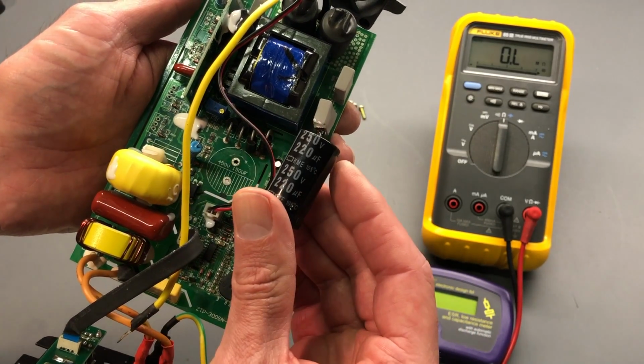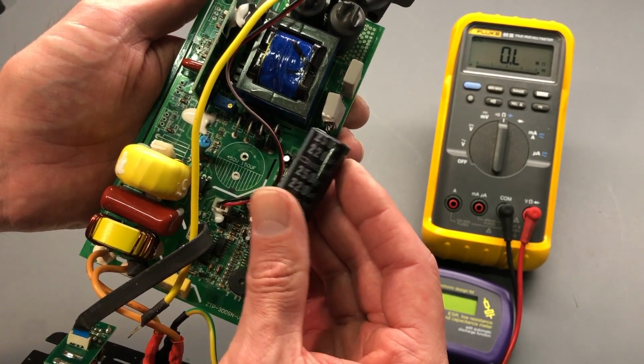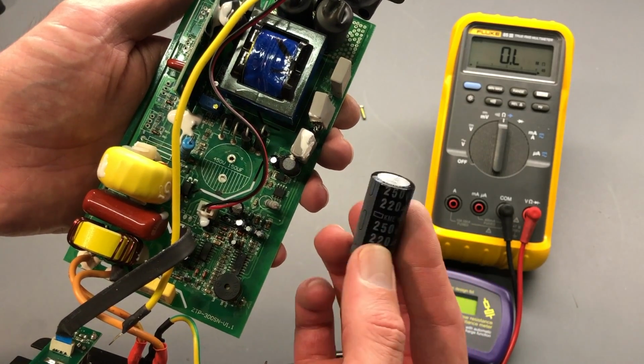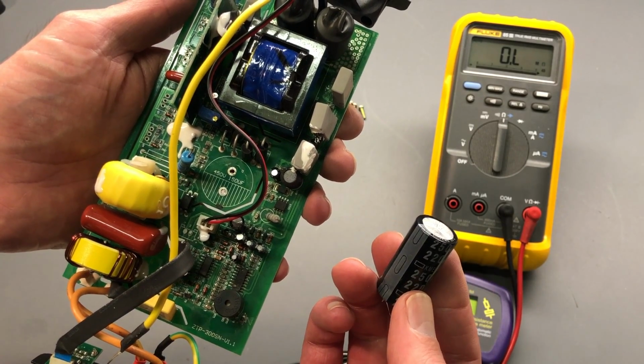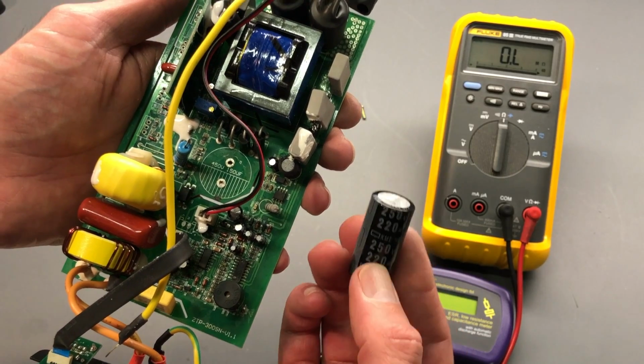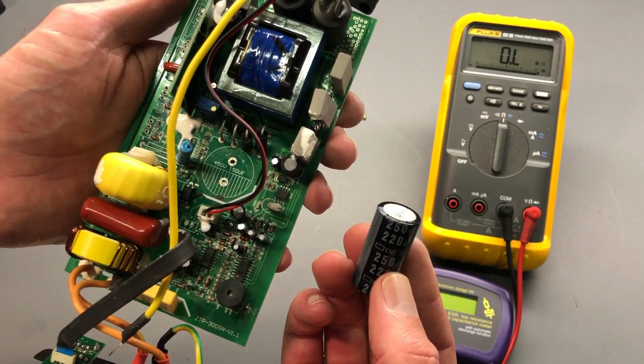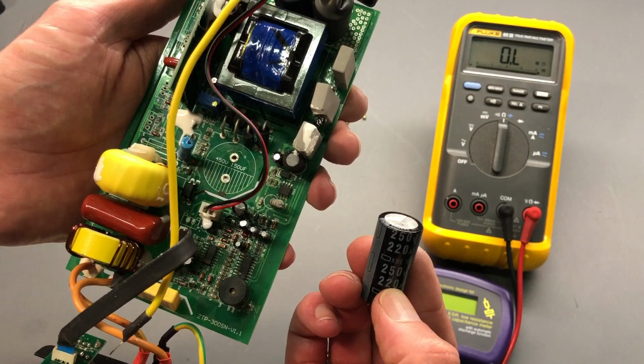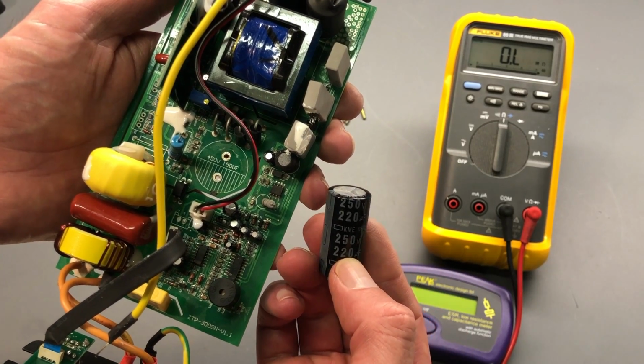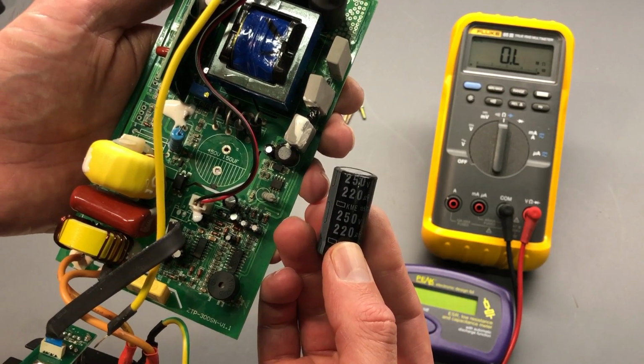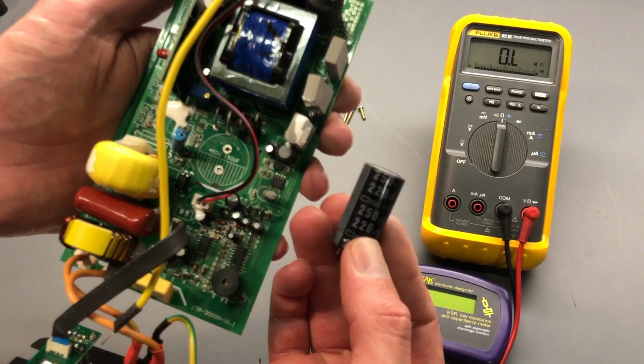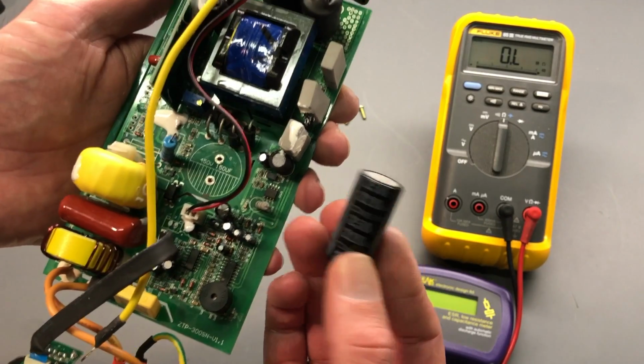150 microfarad, this is 220 microfarad. Seems like the higher capacitance should be okay, I don't think that'll be an issue, I'll stay with that. But if the trade-off is that, if it's 220 microfarad and 450 volts, it just may physically be too big. So to get the higher voltage, maybe the capacitance will have to be a little bit less. I'll have to look and see what's available.